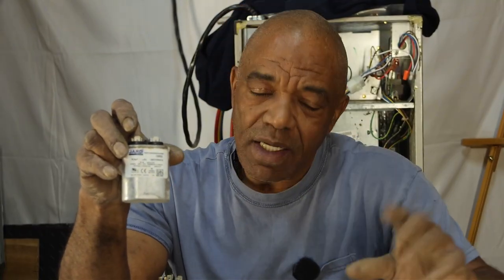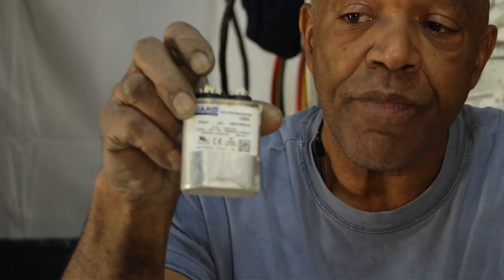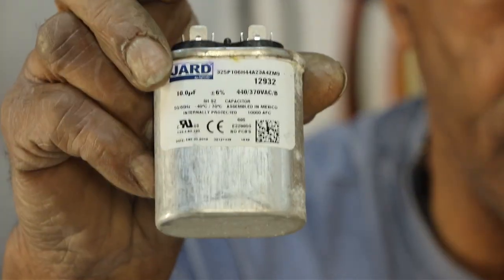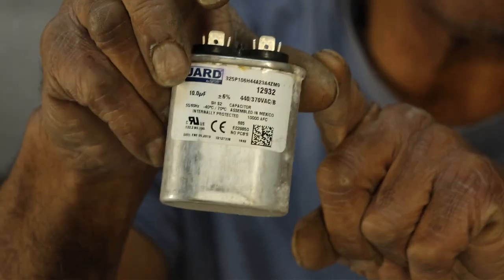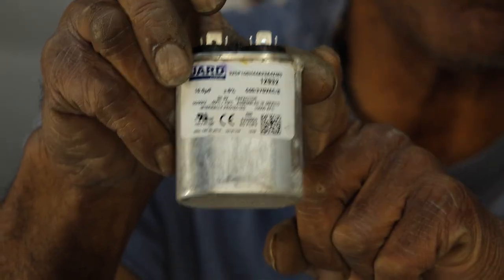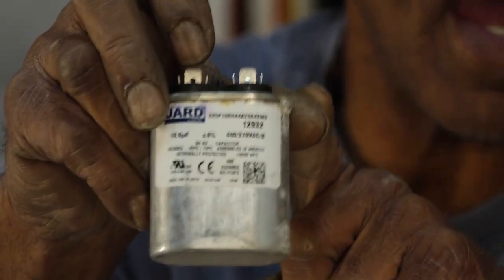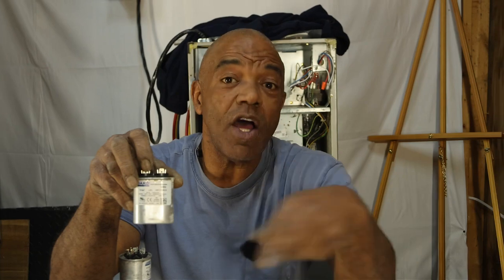They modulate, they're different from the old, but you're still going to run across a lot of systems that have capacitors on the indoor fan motor. Now, one of the ways that you can check this capacitor, if you're thinking your capacitor is bad, one of the things that'll happen is your fan motor won't run when there's a call for heat or a call for air. But sometimes if you reach in and you turn the fan motor and it starts running, your capacitor is bad.